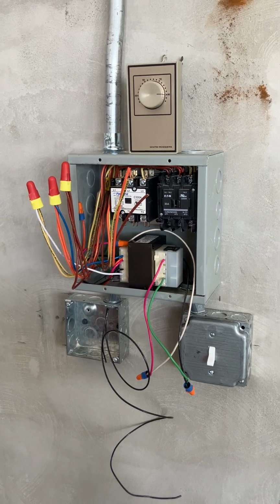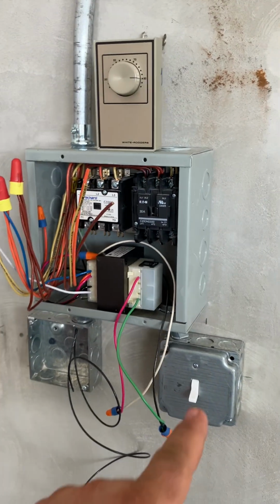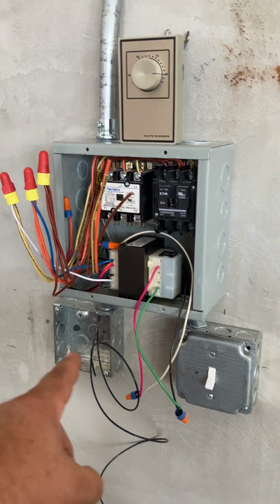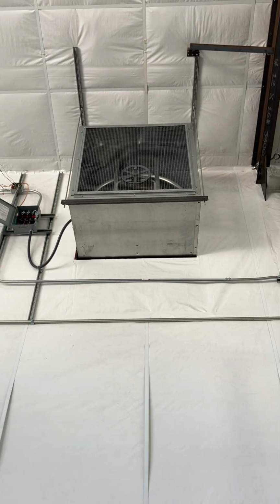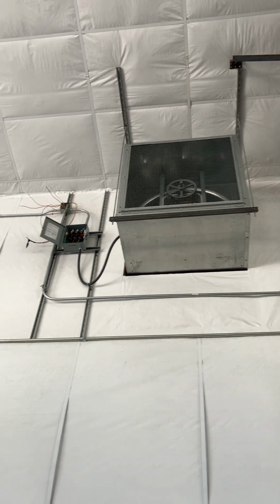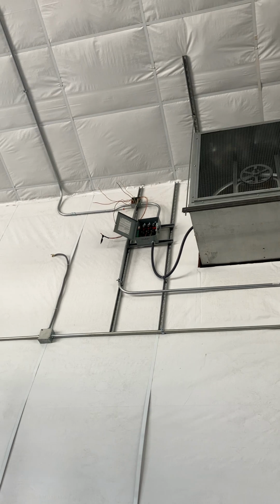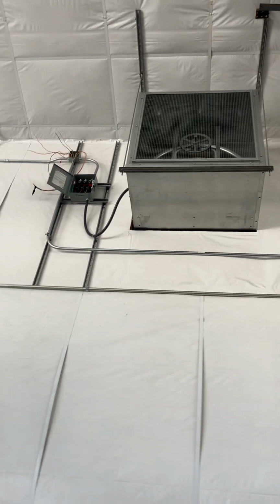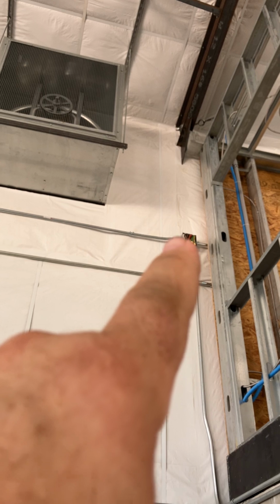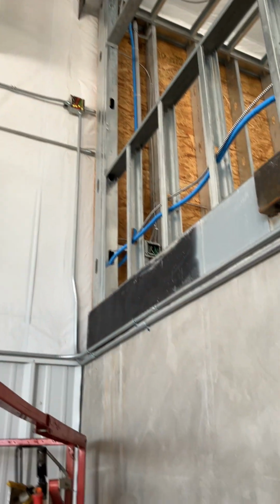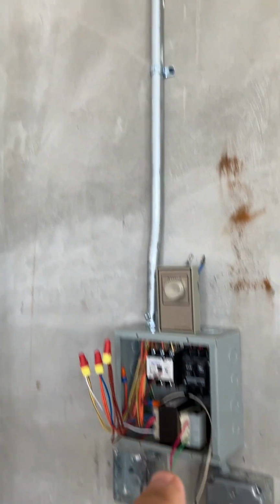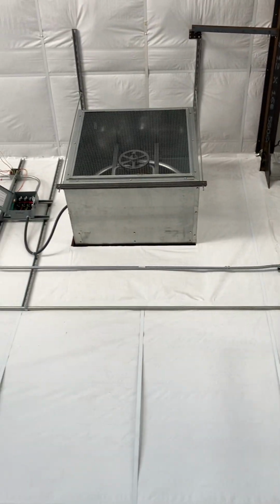All right, so what we're doing today is setting up an array of switches, a switching array as I call it, for two exhaust fans. You see one of them straight up above us with its disconnect and feeder pipe and all that. And then a pipe running down below to a junction box, which not only feeds down to the switching array, there it is, but also across behind that wall to the other exhaust fan way on the other side.